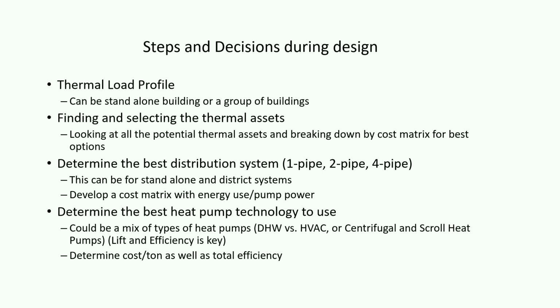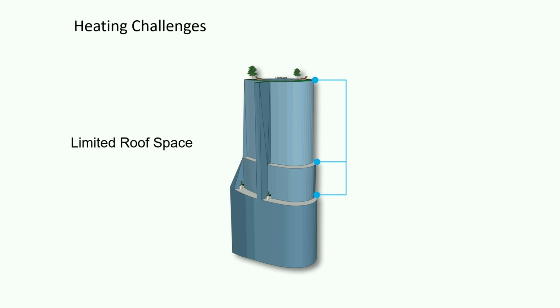And then there are a lot of different ways to pipe up a system schematically within a tall building. Most of what we're talking about today is a traditional heat pump in unit application. Every now and again with some tall buildings, especially in the high-end condo or high-end market rate markets, they may end up doing fan coils with 4-pipe systems to keep all the compressors and main components in a mechanical room versus in suite. But most of the time you're looking at in-suite heat pumps, which is what Jason's going to talk about, and then of course the heat pump technology, which again he'll get into. So again, we've got limited roof space, and that goes to putting all your boilers up there if it's traditional, your cooling towers, all that stuff that goes on the roof.